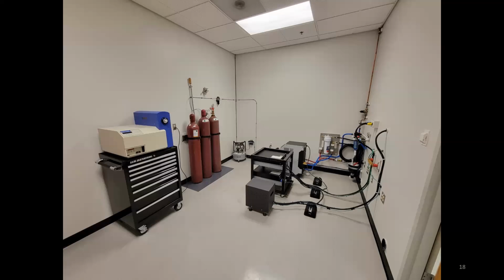And so the only thing that's keeping us from using this right now is we're waiting on a 25% oxygen, 75% argon tank. And for some reason, it's taken 6 weeks to get it because it's all backed up in California. That's to clean the sample, no? Yeah, so what we do is run that oxygen argon mix in the plasma over the top of your sample. When you create that plasma, it's going to oxidize any hydrocarbons that are on there, and then they'll turn into carbon dioxide when they get out of there.